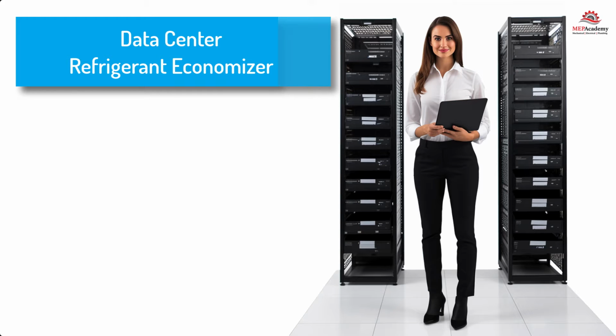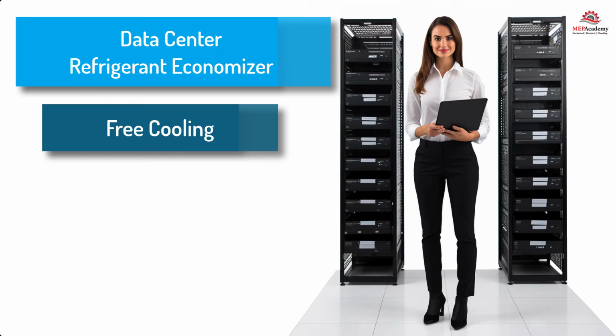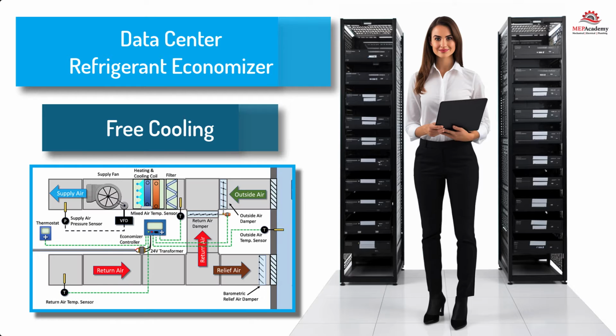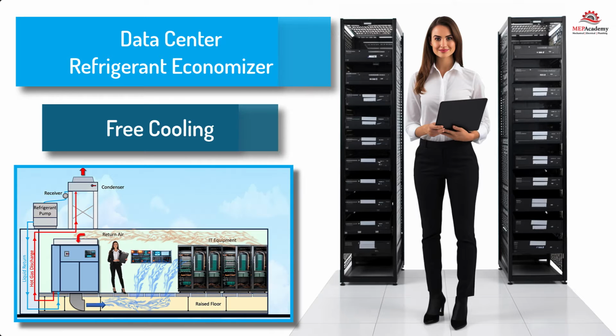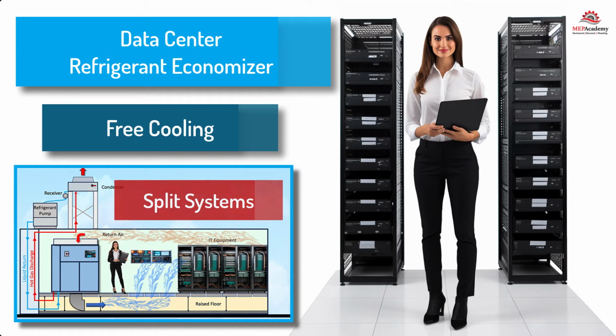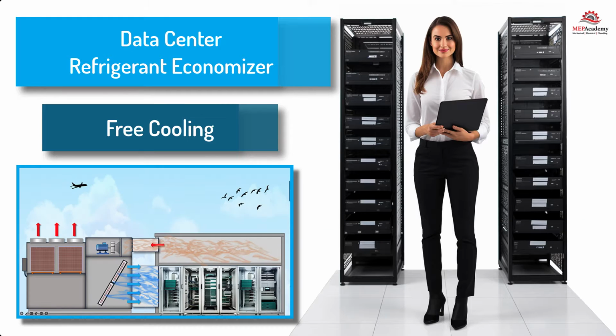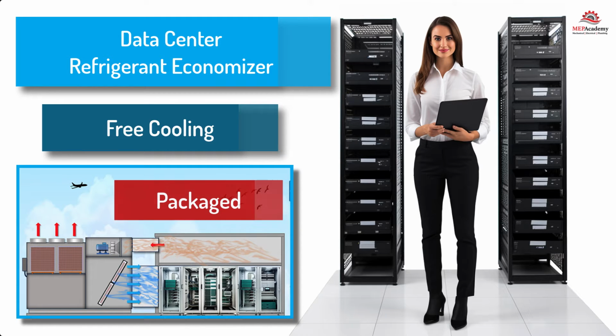Data center refrigerant economizers. We'll explain how a free cooling system with a refrigerant economizer works in data centers. Unlike air economizers, which use outside air for cooling, refrigerant economization systems operate differently. These free cooling systems come in a split system or package unit version with multiple configurations.